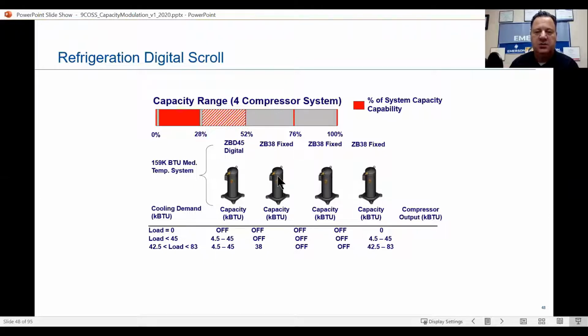So in other words, instead of being 45 as it was, now that we have this fixed compressor at 38, this is going to ramp down to like a 7 BTUs, okay? So that's what it's going to do. It's going to match the load. And as it calls and keeps going up and the store starts to fill, it's going to max out. We're going to get up to that 45 and that 38, okay, which would be what, 83, I believe? Okay, once it hits that peak, it's going to ask for help from the third fixed compressor.